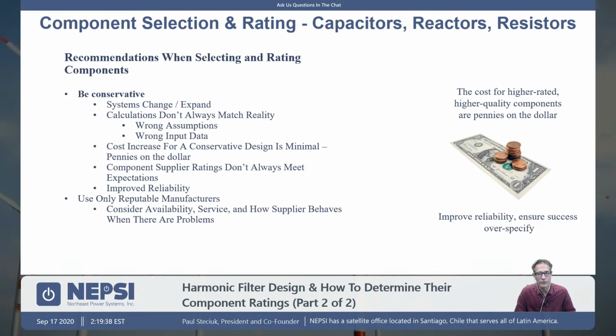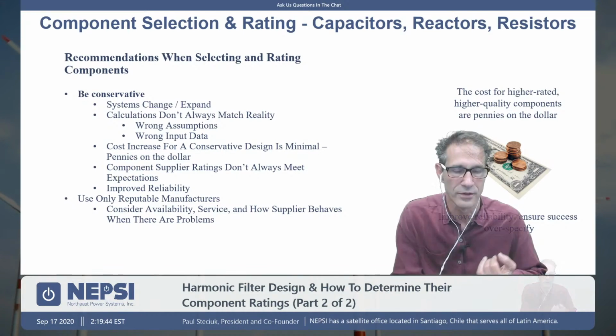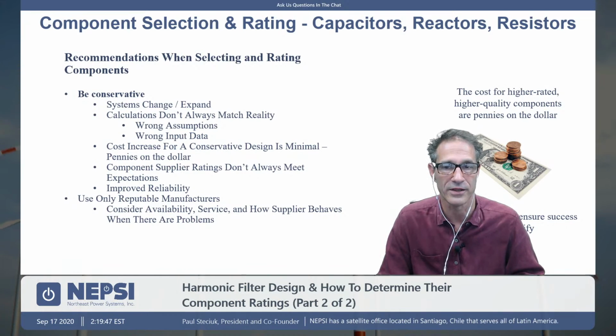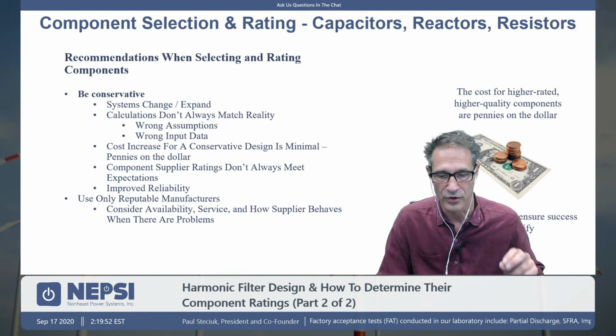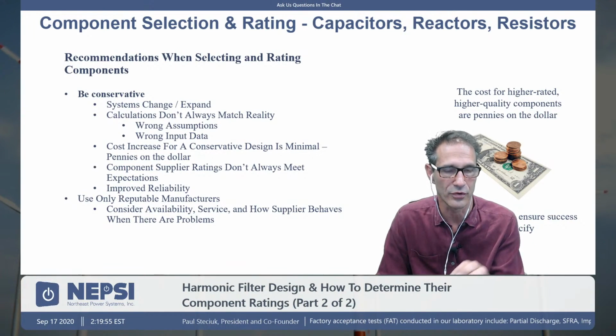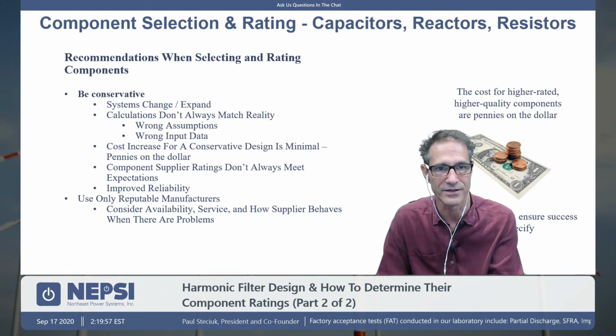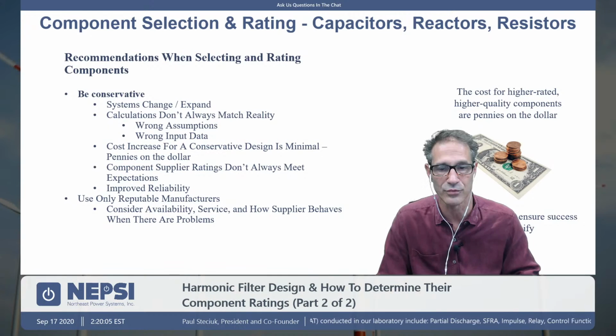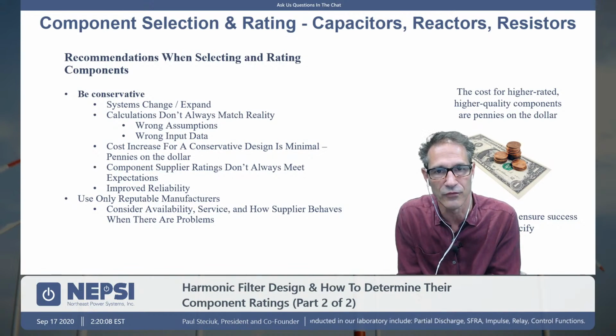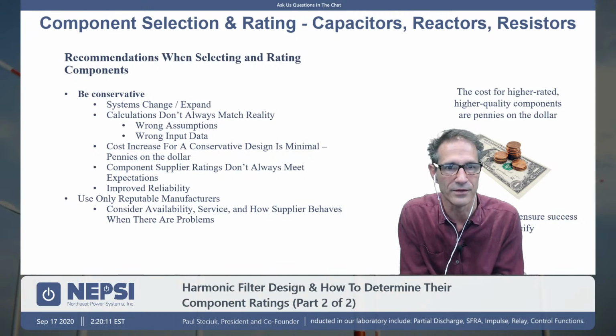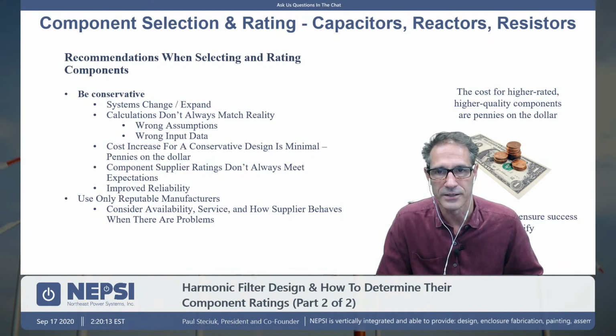You want to make sure that you use reputable manufacturers. Who are you buying reactors from? Make sure that those reactors are being supplied by a company that is in the business of supplying harmonic filter reactors. Harmonic filter reactors, whether they're air core or iron core, are a different phenomenon. It's not like a transformer. Oftentimes, engineers, especially those developing specifications, will feel that if you can build a transformer, you can build a tuning reactor, and you cannot. They're totally different. It is much more difficult to build an iron core harmonic filter reactor.